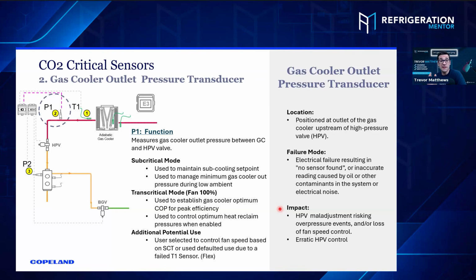So this is what you really need. This is why it's critical. It's not just doing the outlet of the evaporator for your superheat temperature or your return air or your defrost termination. It's not just one thing. It's doing 5 things. No, absolutely. And you may say, okay, but that one being out of control means this high pressure valve can't manage, means that my flash tank pressure's out of control, can't manage, my bypass valve doesn't know what to do, my compressors are cycling for no reason, and then it just keeps going round and round until the system crashes.